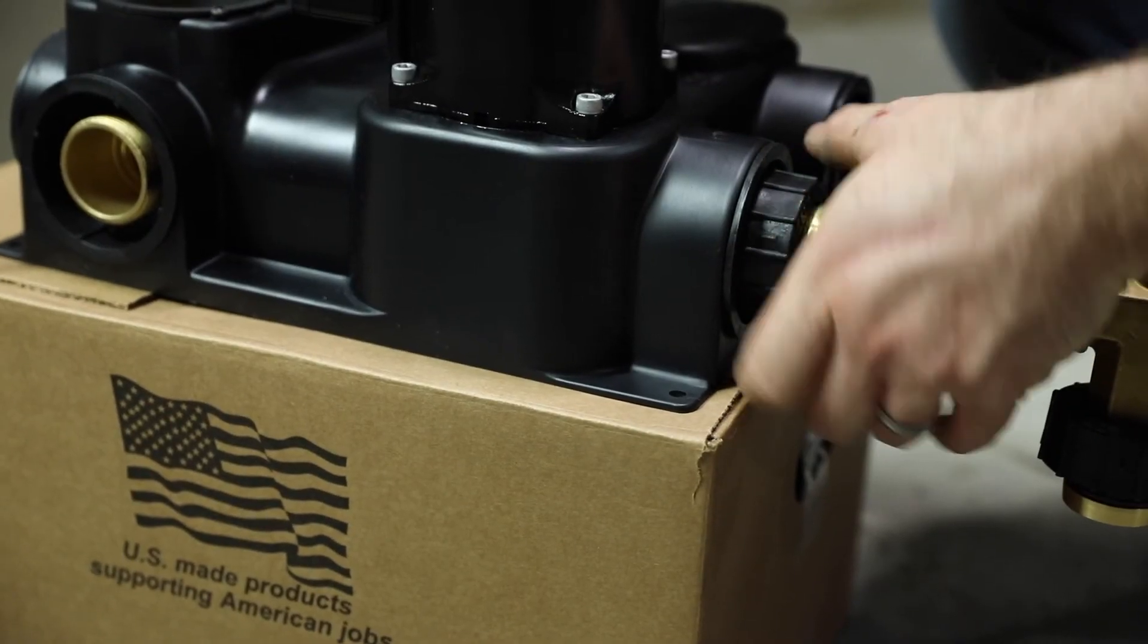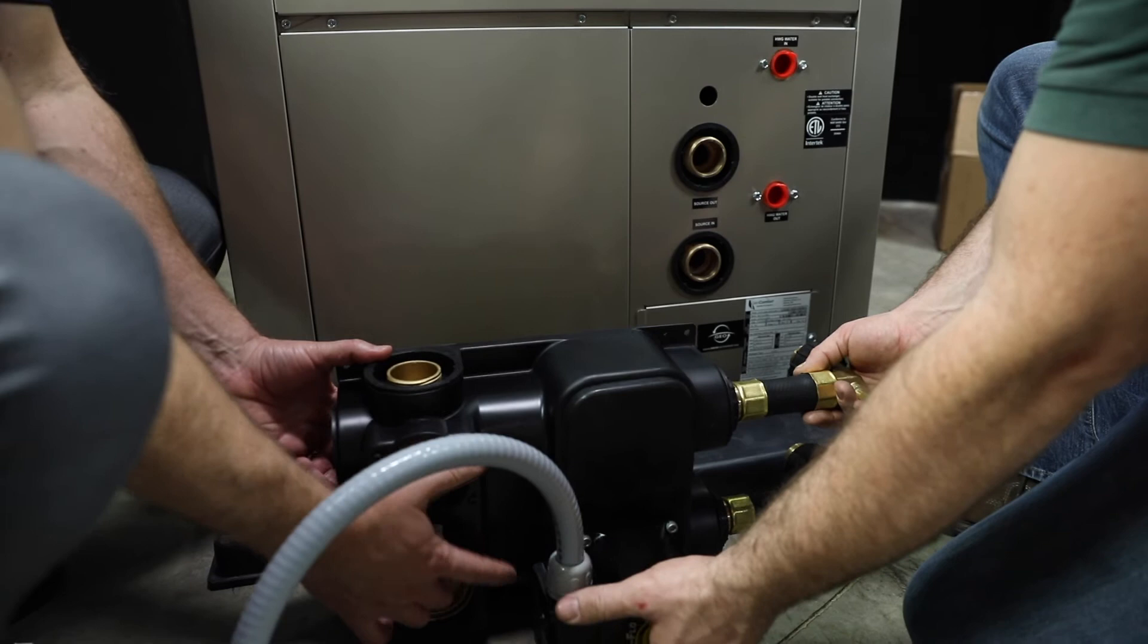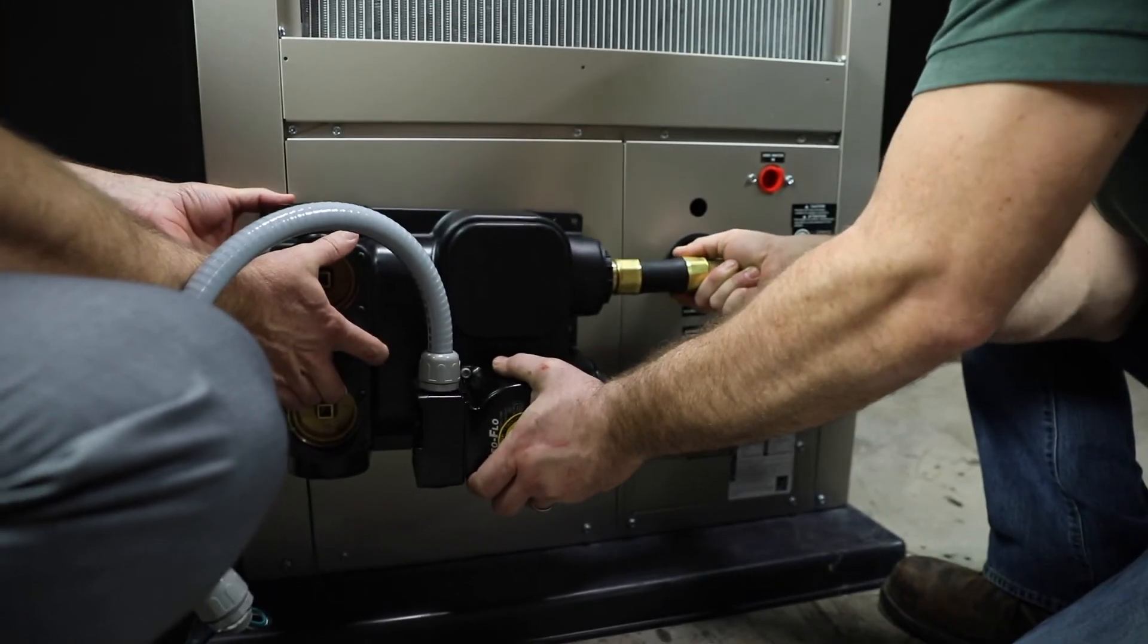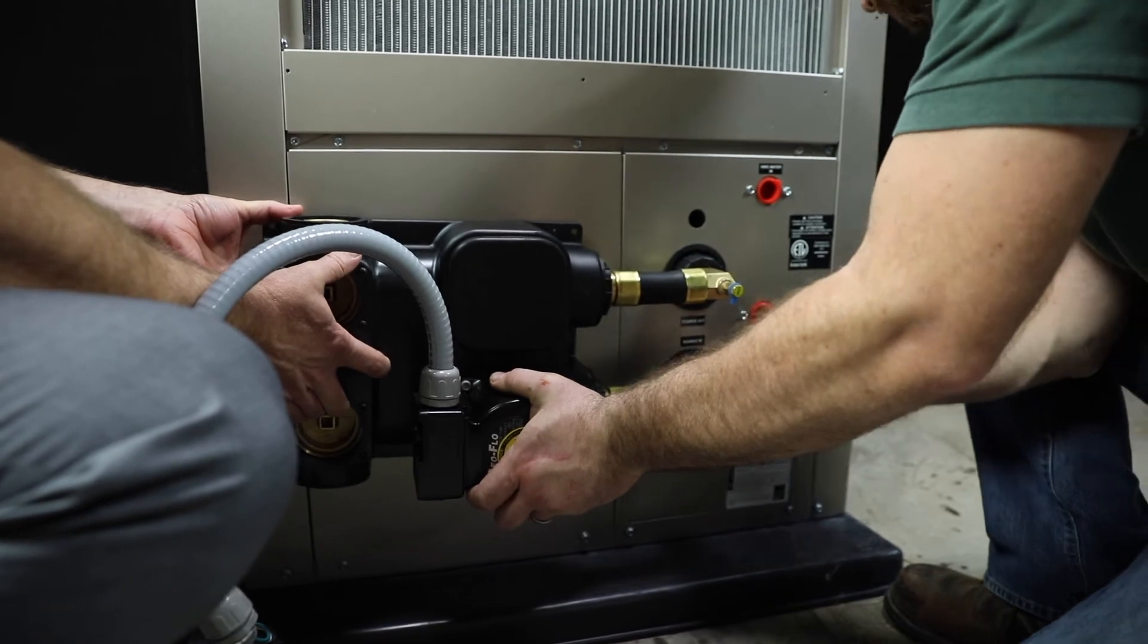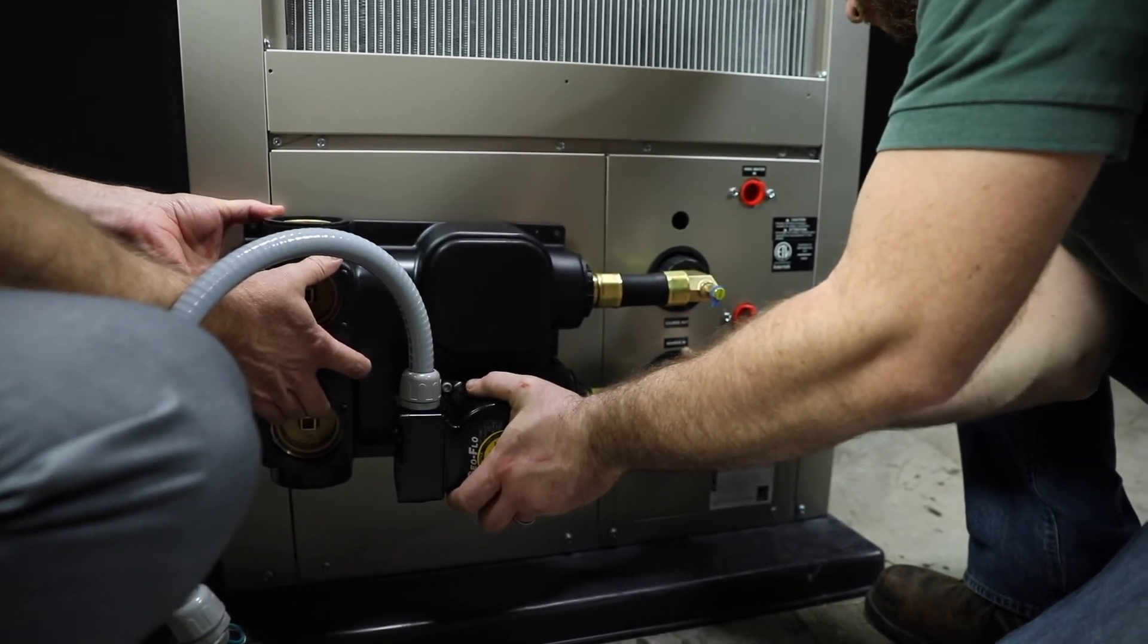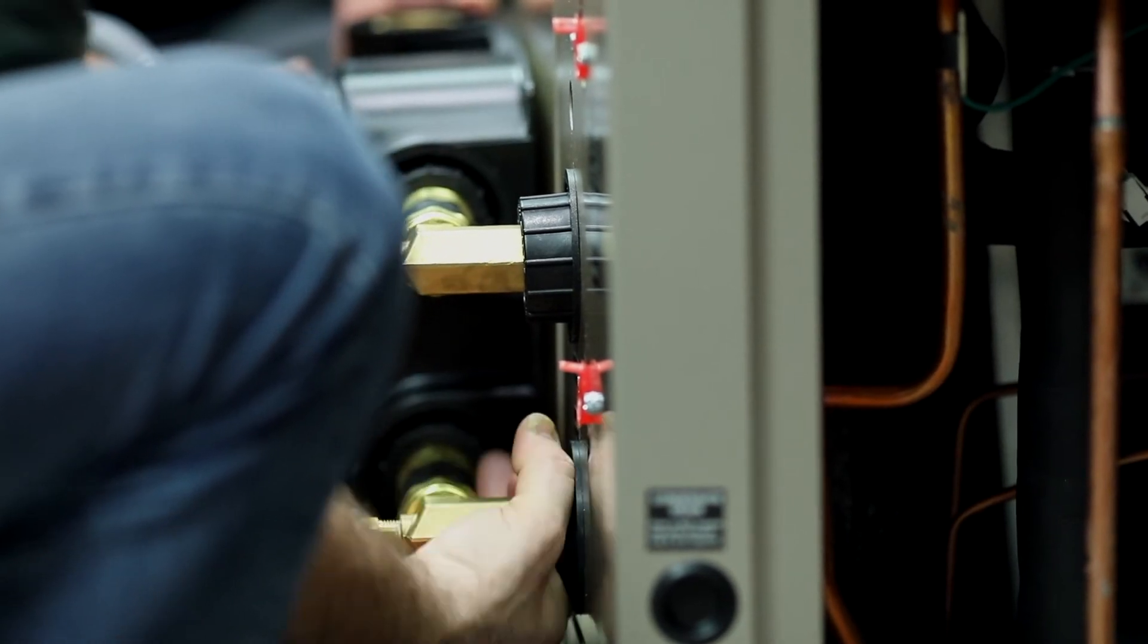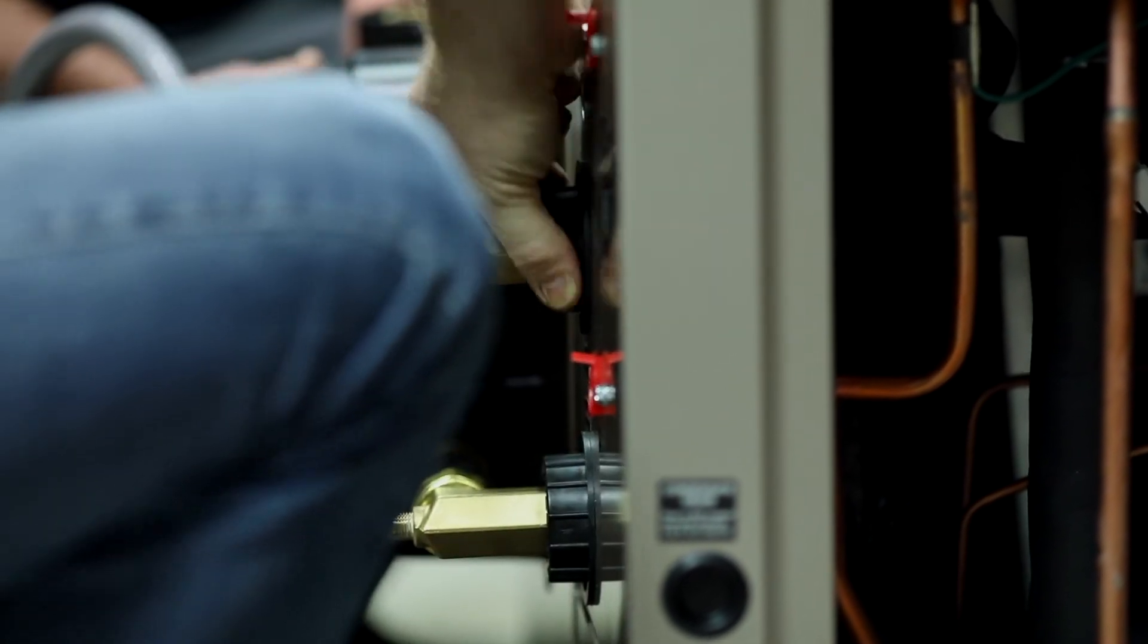Assemble both fittings onto the flow center. For the next step an extra pair of hands is helpful. Another option is to place blocks under the flow center to line up the flow center fittings to unit connections. Lightly hand tighten all double o-ring joints. These will be fully tightened at the end of the installation.